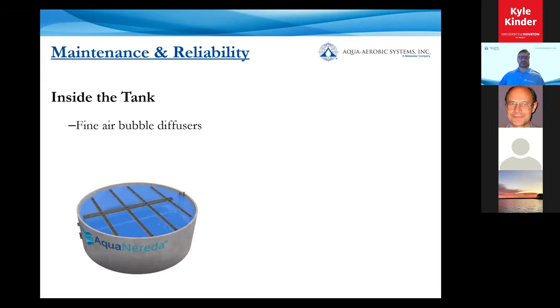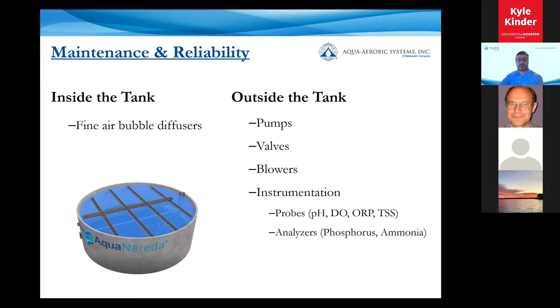And so when we take a look at the last piece, one of the bigger advantages of Nereda is the maintenance and reliability. When you look at the tank or the reactor, it operates much closer to a clarifier than a biological treatment system because there are no moving parts within the reactor itself. So everything is fixed. The effluent weirs are fixed. The fine bubble diffusers and the influent distribution grid are fixed. And so there really are no moving parts within the reactor that require ongoing maintenance. And so from a reliability standpoint, it offers an enhanced level of reliability. Everything requiring maintenance, like pumps, valves, blowers, instrumentation, is located outside of the tank.